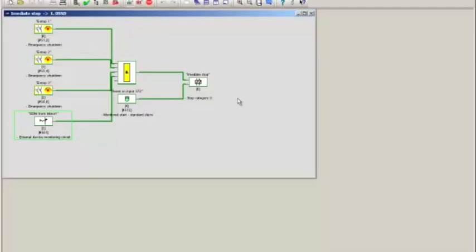Now, let's do this. I'm going to create a fault, and the way I create this fault is I pretend that my motor contactor is bad and the signaling, the auxiliary contacts, do not work properly. The easiest way for me to simulate that is by disconnecting the wire that connects the feedback into input S81.